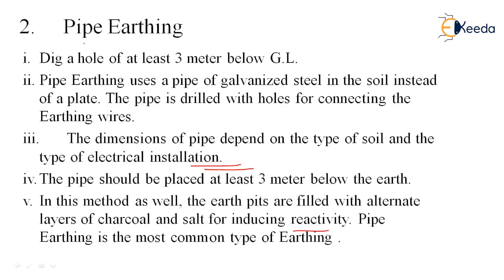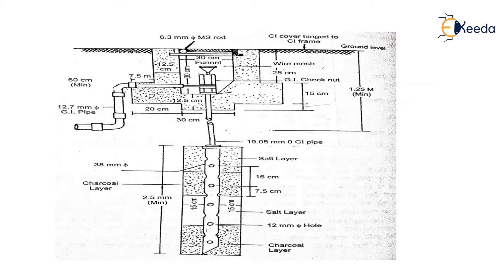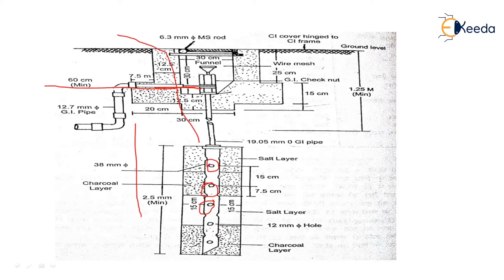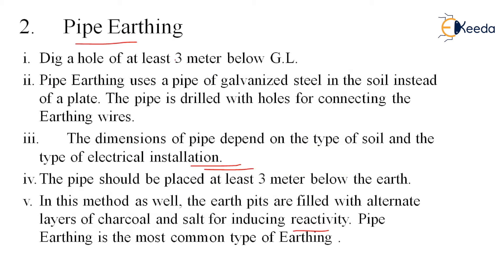Instead of a plate, the most common type is pipe earthing. The procedure: dig the pit downward, fix the pipe vertically, ensure holes are present in the pipe for current discharge. Connect the wire to the pipe and bring it out to the surface. A funnel can be inserted here as well for watering. Fill the pipe and surrounding pit with charcoal and salt. Flush with the ground level and cover it. Maintain moisture throughout the year. This is the working of the pipe earthing system.